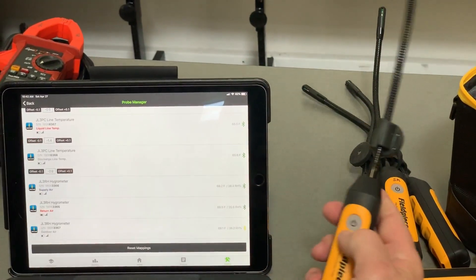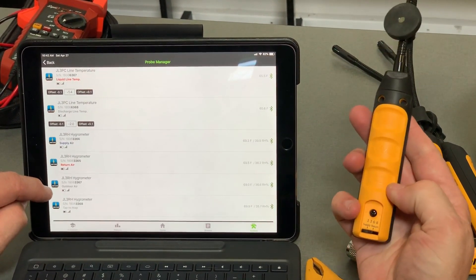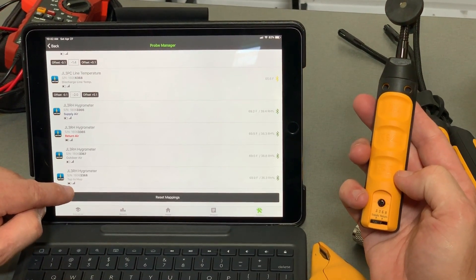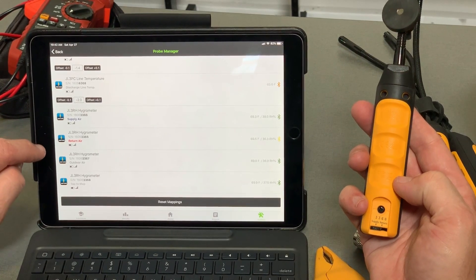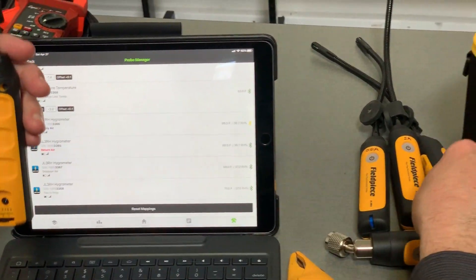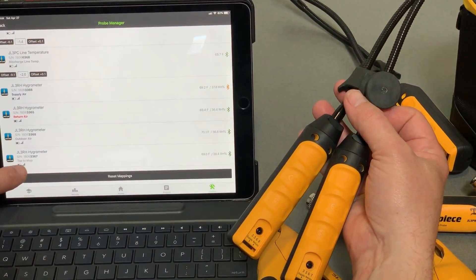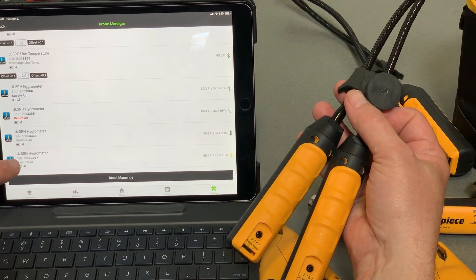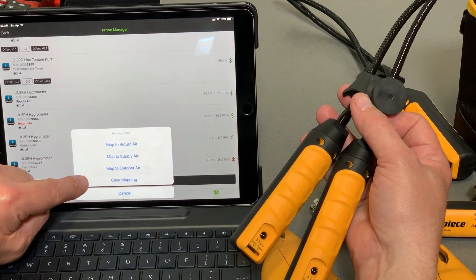If I turn on another probe at any time during this, what you're going to see is that probe is going to drop in at the bottom. So this one's 0368, and now that's tied into the bottom of the Probe Manager. You can turn them all on at once or turn them on one at a time and they're going to pull in, and then we can tap to map. So this one's 0367 and 0368. The 0367 is my outdoor air probe. If I take and map 0368 to outdoor air, what's going to happen is 0367 is going to drop to the bottom on maps.